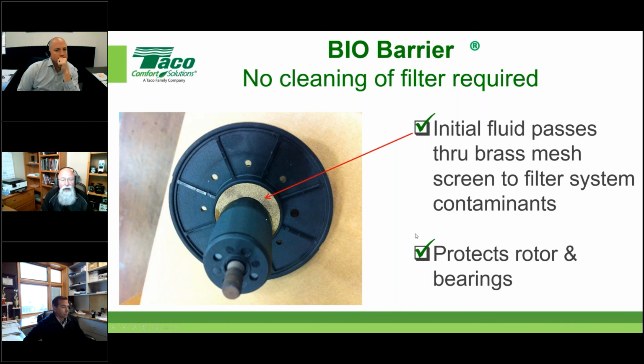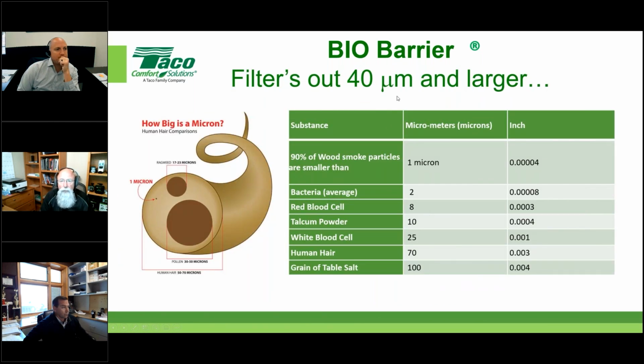Not to say that I've never seen one of these gooped up. Now, the filter media does a really good job, but it only goes down to 40 microns. And 40 microns is actually pretty small. It's about the size of the pollen floating around, causing our eyes to water and sneeze, and our bodies to start attacking. So when we're talking microns, we're talking really, really small stuff, but some of that BIO or black iron oxide would be smaller than 40, and that's problematic with anybody's equipment. This is a self-preservation type design, but we can only go so far. It's done a really good job for the most part. And we're reasonably sure people are going to copy us on this feature as well.